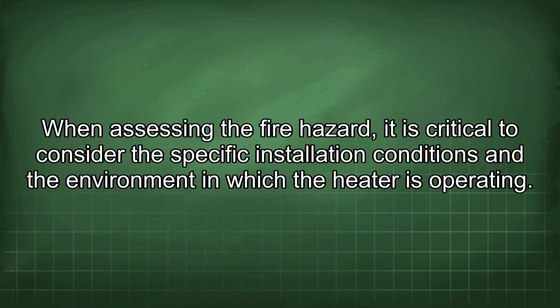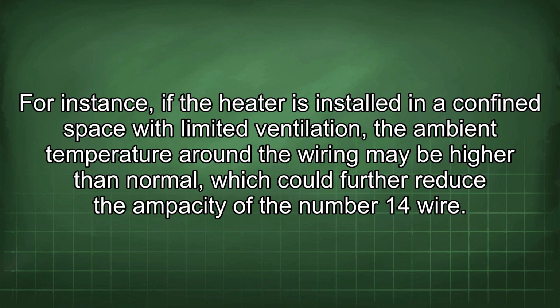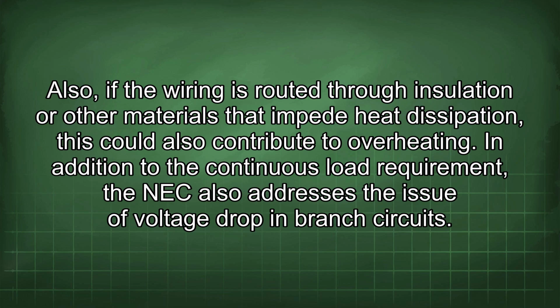When assessing the fire hazard, it is critical to consider the specific installation conditions and the environment in which the heater is operating. For instance, if the heater is installed in a confined space with limited ventilation, the ambient temperature around the wiring may be higher than normal, which could further reduce the ampacity of the number 14 wire. Also, if the wiring is routed through insulation or other materials that impede heat dissipation, this could also contribute to overheating.